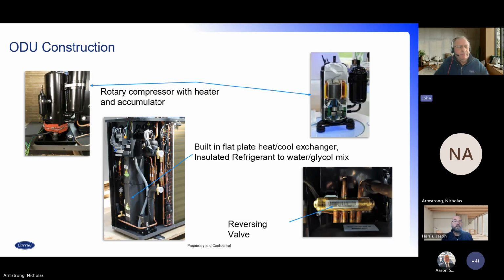A bit more in depth as far as what the components look like. The rotary compressor there to the left, the braze plate heat exchanger built into the outdoor unit. It is insulated to have a maximum heat transfer between the outdoor unit back into the indoor unit and into the home. And down on the bottom right-hand side of that slide, you have the reversing valve. The reversing valve allows the outdoor unit to either provide heating or the cooling option for the home.